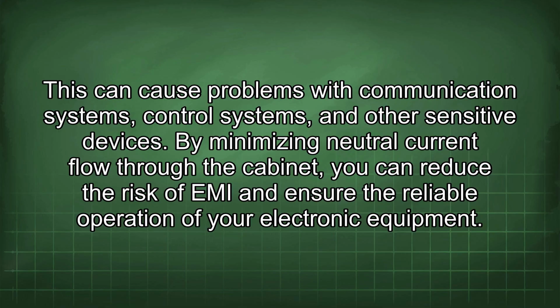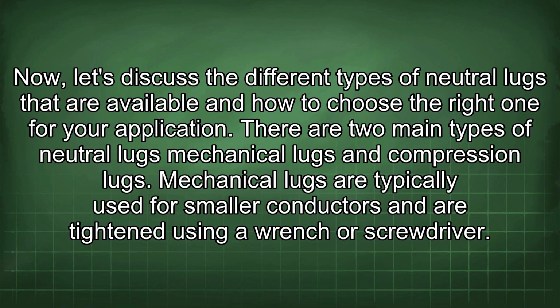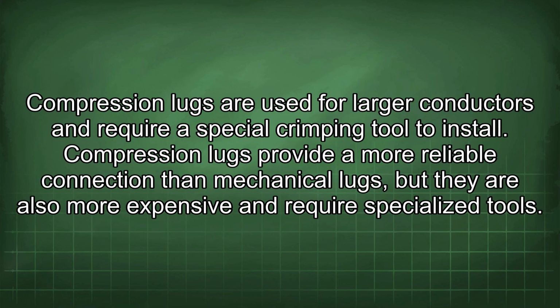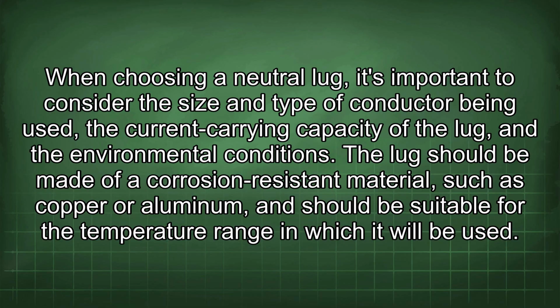Now, let's discuss the different types of neutral lugs that are available and how to choose the right one for your application. There are two main types of neutral lugs: mechanical lugs and compression lugs. Mechanical lugs are typically used for smaller conductors and are tightened using a wrench or screwdriver. Compression lugs are used for larger conductors and require a special crimping tool to install. Compression lugs provide a more reliable connection than mechanical lugs, but they are also more expensive and require specialized tools. When choosing a neutral lug, it's important to consider the size and type of conductor being used, the current carrying capacity of the lug, and the environmental conditions.